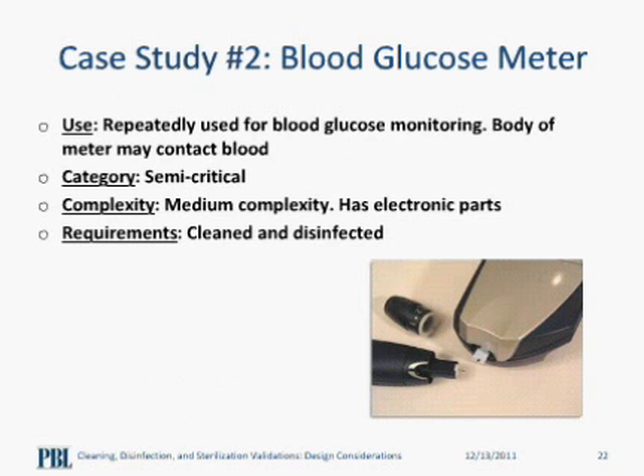For this validation, we did not validate the lancing device because this component is usually disposable. We only validated the cleaning of the meter. Although the meter does not prick your finger, your pricked finger can still come in contact with the device. So this device is categorized as semi-critical, which means that this device needs to be cleaned and disinfected. The meter has buttons and electronics, so it is medium in complexity due to the fact that you have to take care in not getting any liquid into the device.